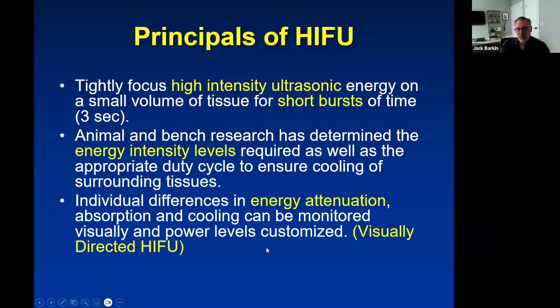So we can change the energy intensity levels. And the other thing that we have to be cognizant of is that the energy does not necessarily transmit completely, depending on what's happening within the tissue itself. There's some absorption, some cooling things that take place. So is there a way that we can actually monitor on a literally second-by-second basis to see if we are achieving the energy or the temperatures at the focal point, the point where we're delivering energy, that we believe we are, or we hope to achieve in treating with HIFU?